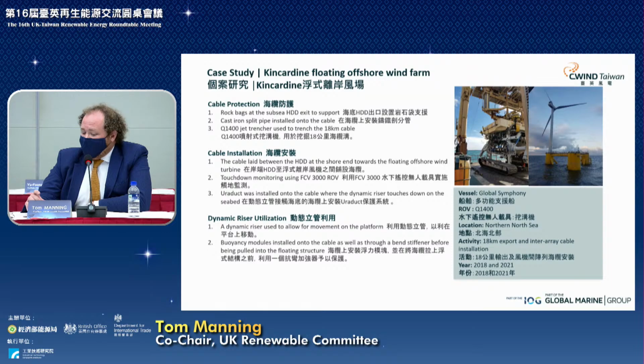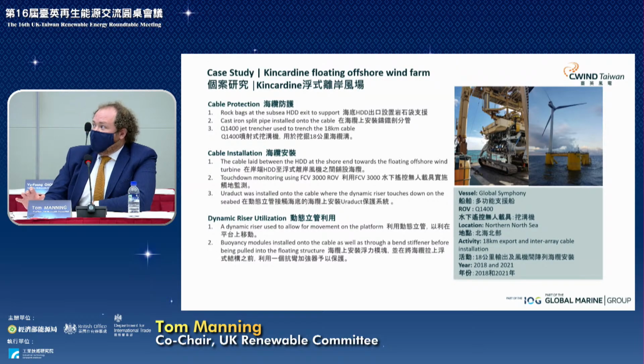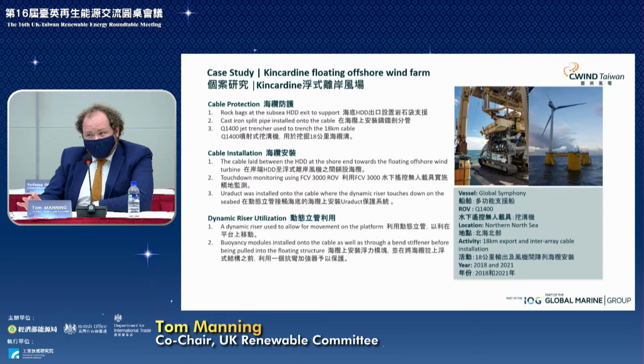At the point where the cable is installed and becomes dynamic cable up to the foundation, we use touchdown monitoring with a work class ROV. At various points during that dynamic riser's journey from the seabed to the floating foundation, we installed Uraduct and flotation sections to make sure the buoyancy modules kept the cable in the right position for us to pull it into the floating structure.